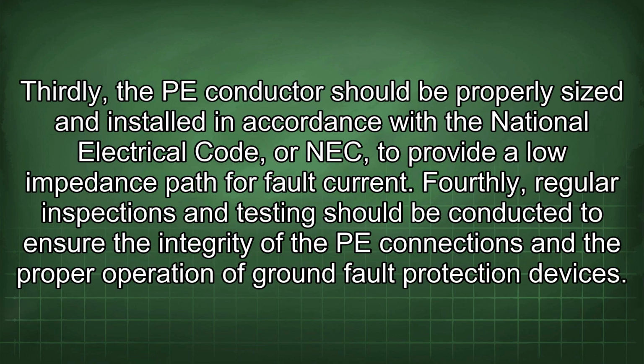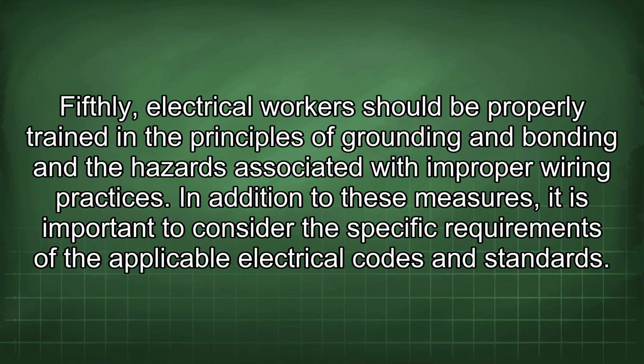Thirdly, the PE conductor should be properly sized and installed in accordance with the National Electrical Code, or NEC, to provide a low impedance path for fault current. Fourthly, regular inspections and testing should be conducted to ensure the integrity of the PE connections and the proper operation of ground fault protection devices. Fifthly, electrical workers should be properly trained in the principles of grounding and bonding and the hazards associated with improper wiring practices.